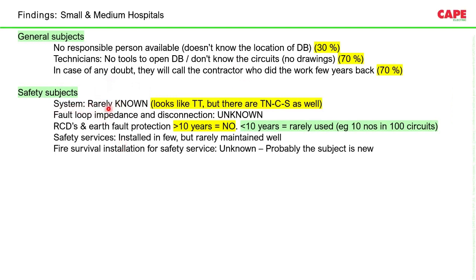With respect to safety, in smaller to medium hospitals, most of the safety requirements are unknown. It's very rarely known. The installation looks like a TT, but most often the system earthing, which is the most important for electrical safety, is a very inefficient way of, let's say, TN-S or TN-C-S. And subjects like fault loop impedance are rarely known. In hospitals which are more than 10 years old, most have no RCD. In hospitals less than 10 years old, of course, in some cases RCDs are used, probably on 10%, 20% of the circuits.